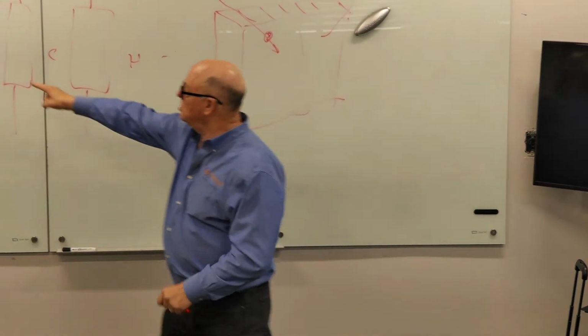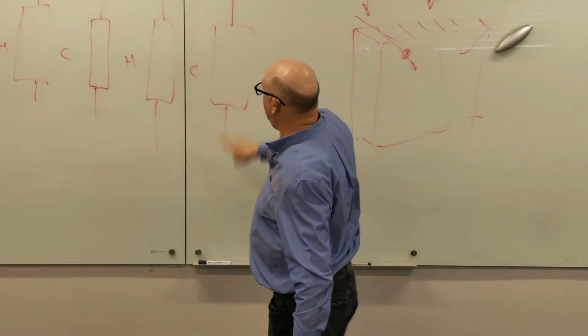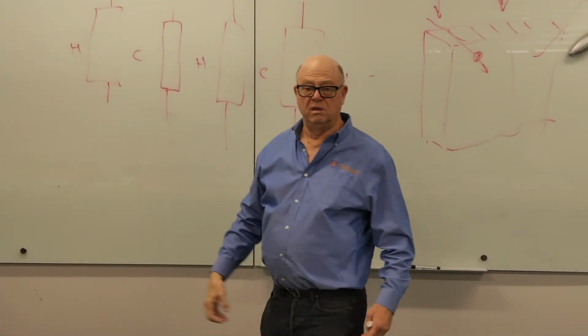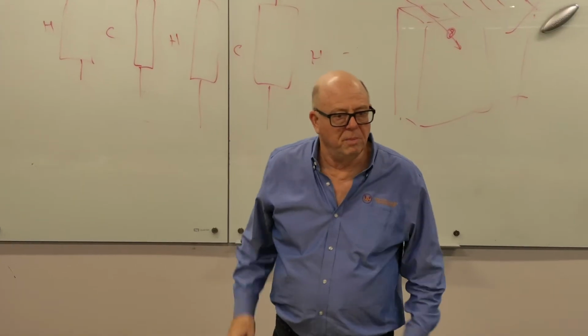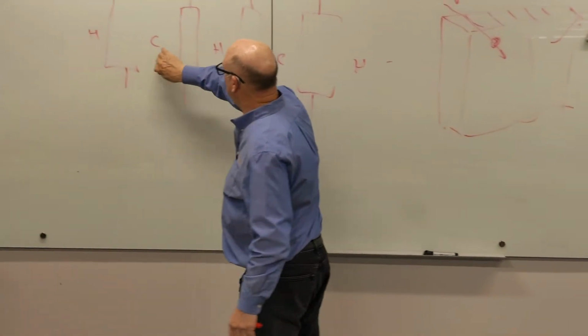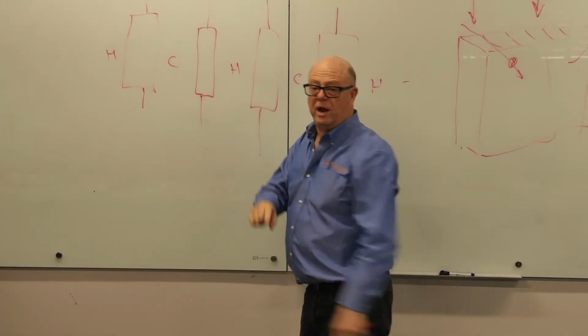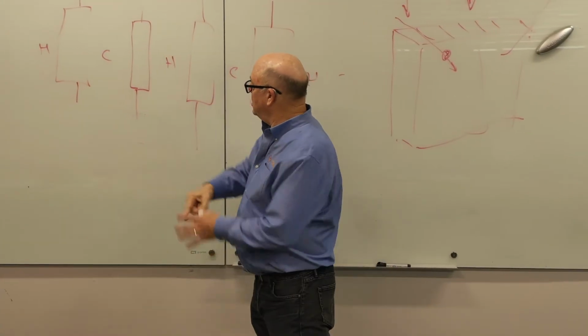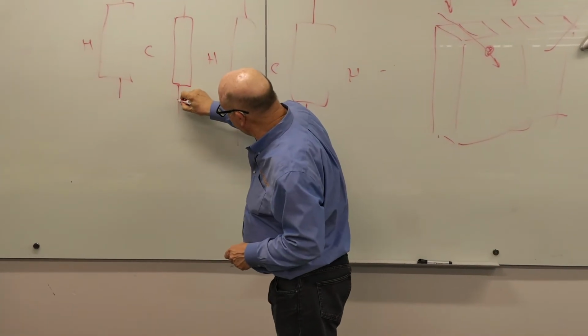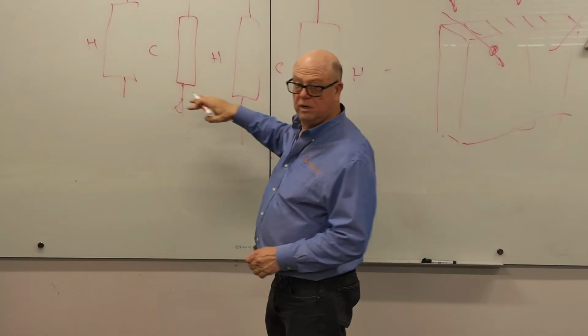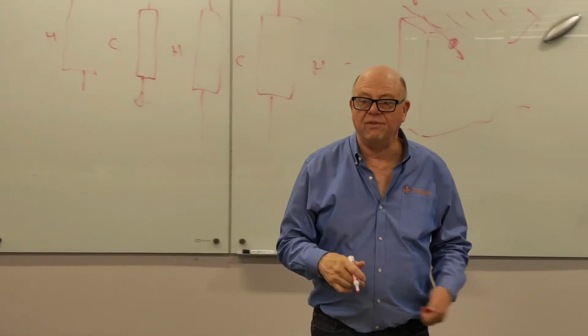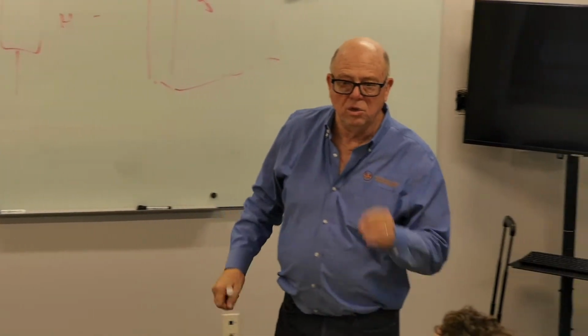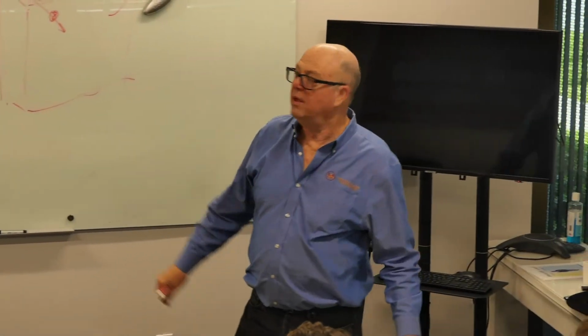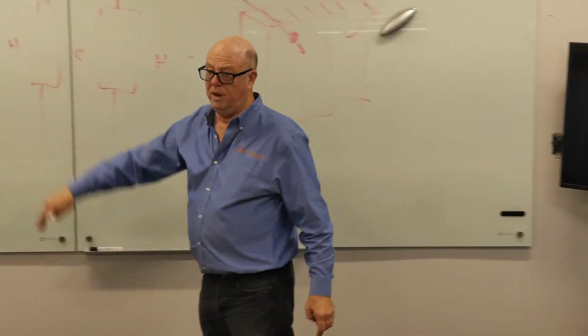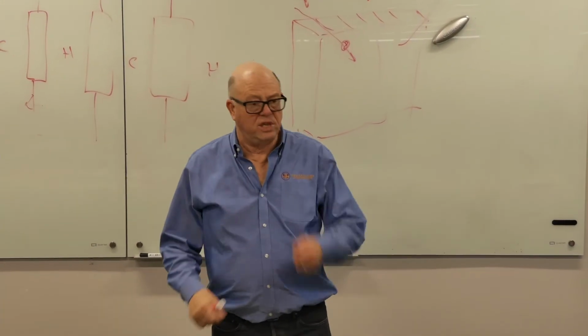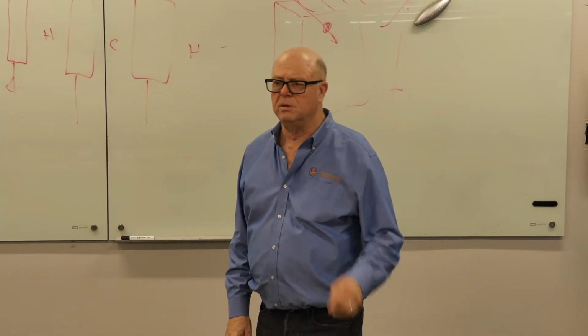So if you can go into an existing one that doesn't have this stuff, which is mostly general contractor work, you might have to reduct, to make sure that you're putting the cold in here, and you're pulling the hot out of the others. And of course, you're in the room, right? So you're going to have a door here in each of these so that you can walk around and have access and all that. But you can pick up easily 15% more server load by doing that, and maybe 20. That's the over time typical.